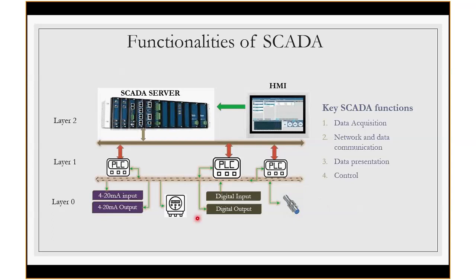If you see layer 0, 1 and 2: layer 0 is responsible for connecting the physical sensors available in the wind turbine or nearby, like multifunction meters installed in the transformer area. All these physical communications need to be terminated in the IO card or communication card of the PLC. This is the layer 1 responsibility, or maybe the layer 0 responsibility.